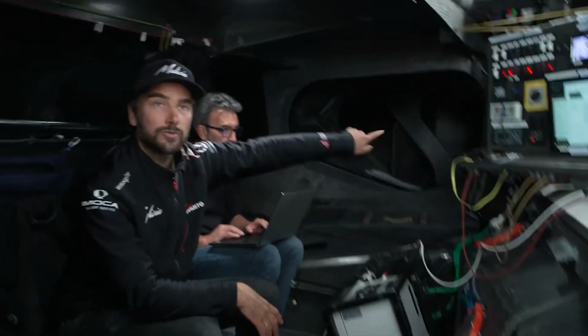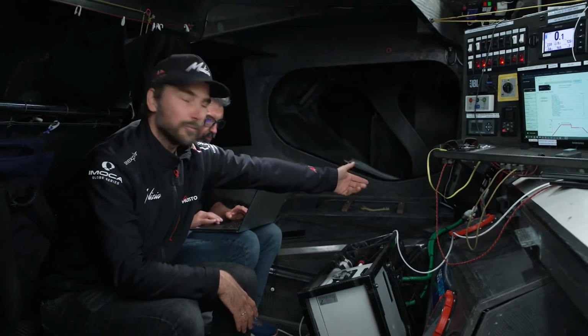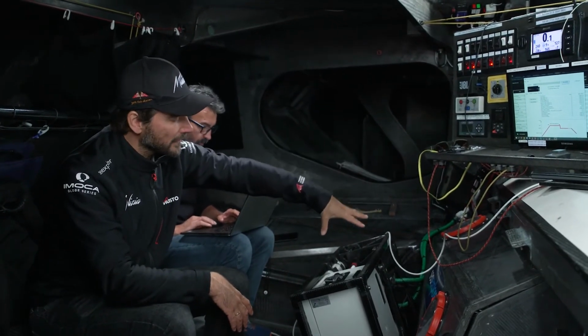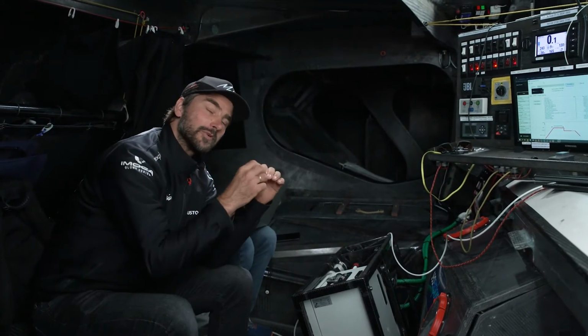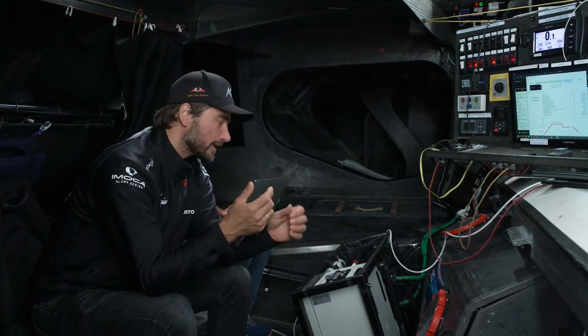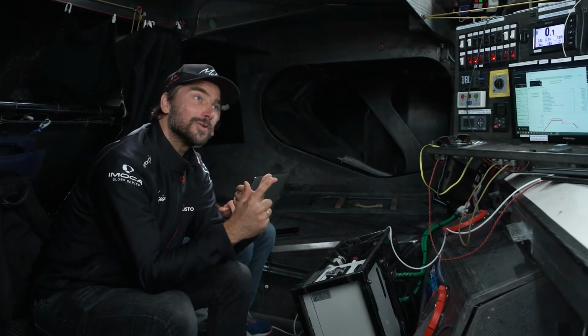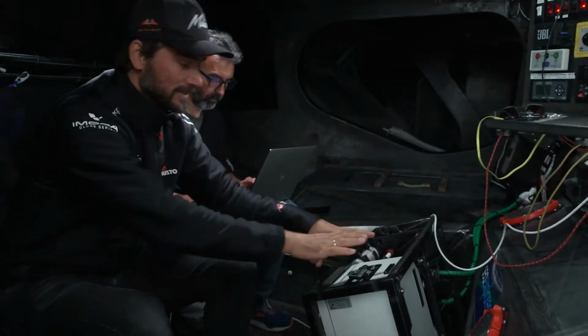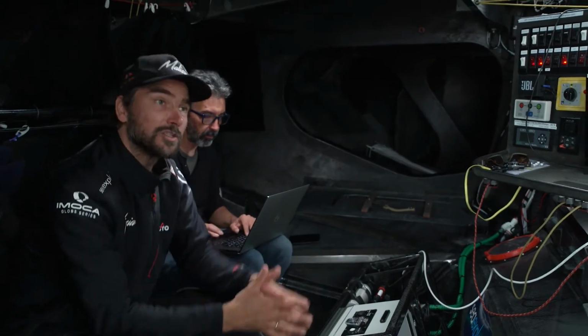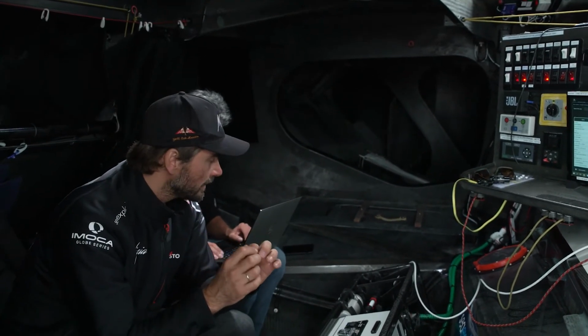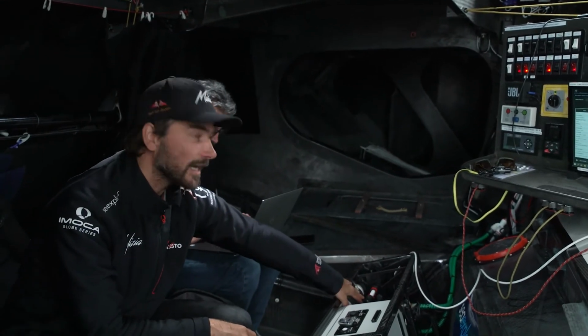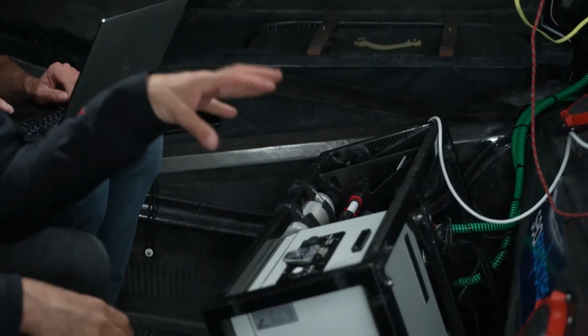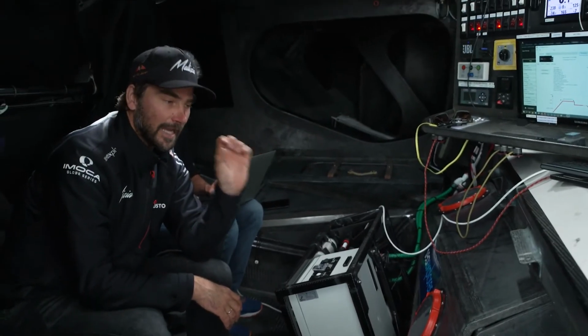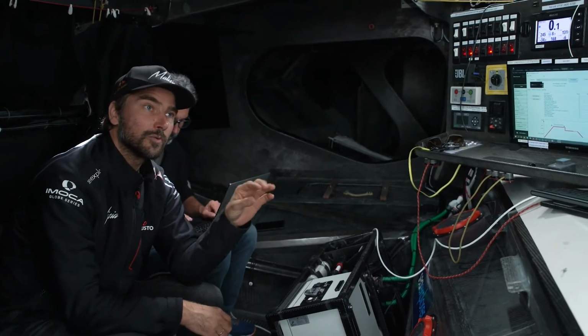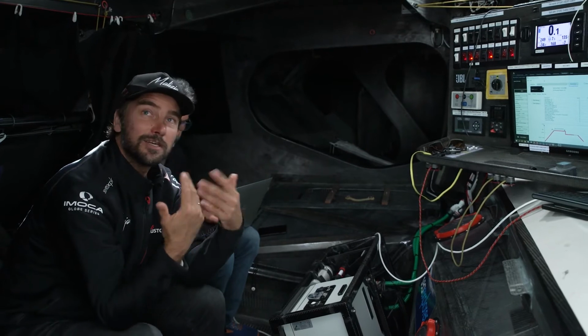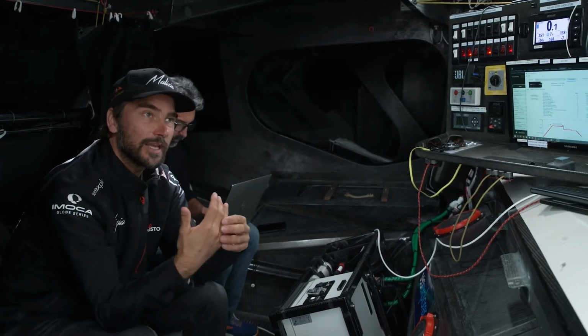This machine pumps seawater through the keel, through the system, and brings the seawater back through the keel as well. And in this white box here, it separates the gas from the seawater. So there's oxygen, but there's CO2 and other gases, but the main thing we focus on is CO2. And that's really a high-tech miracle how they manage in such a small machine to get very precise data. And one particular thing is that we have a calibration gas here. We have a bottle with CO2 gas, so that the sensor of this machine can be calibrated every day automatically with this calibration gas. So we really have the highest scientific standard, and the data gets the highest quality flag in the database.